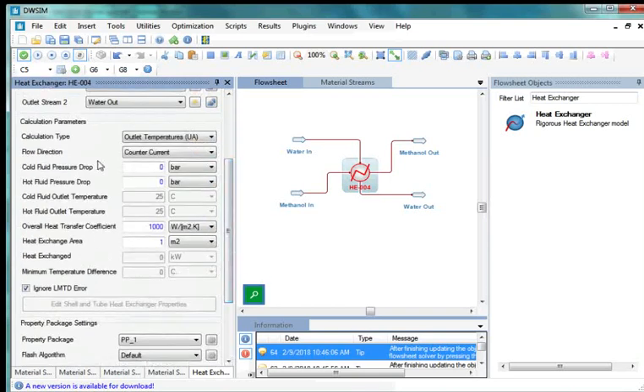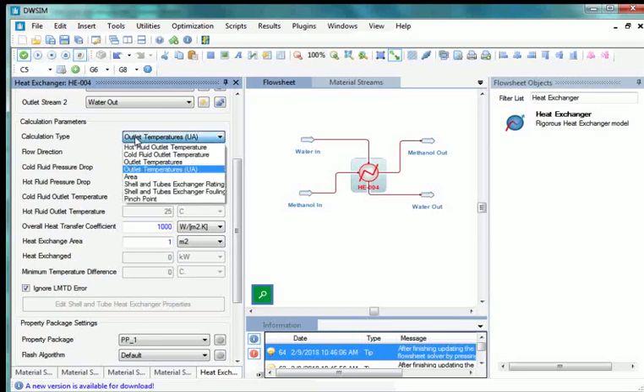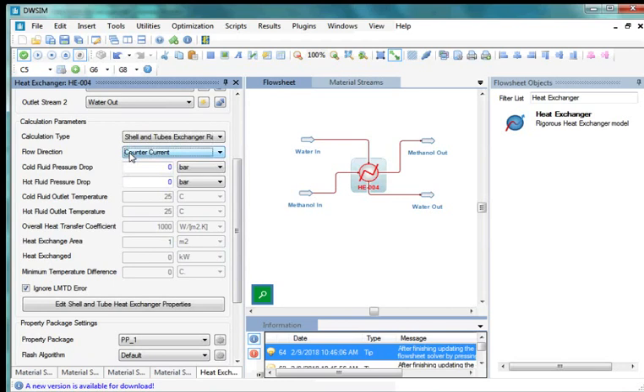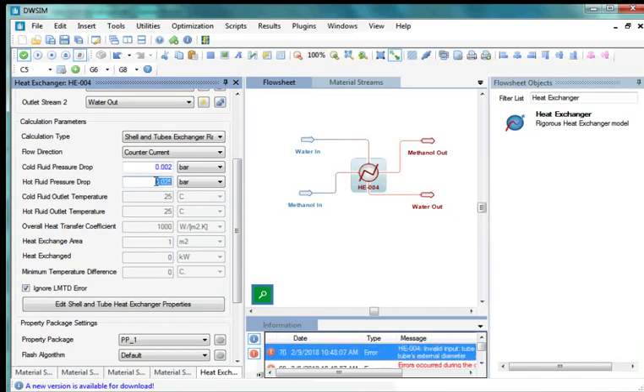Go to the Calculation Parameters section. The first option is Calculation Type. Click the drop-down and select Shell & Tubes Exchanger Ratings. Next, click the drop-down against Flow Direction and select Counter Current. Click on the field against Cold Fluid Pressure Drop and enter 0.002 bar, then press Enter. Click on the field against Hot Fluid Pressure Drop and enter 0.025 bar, then press Enter.